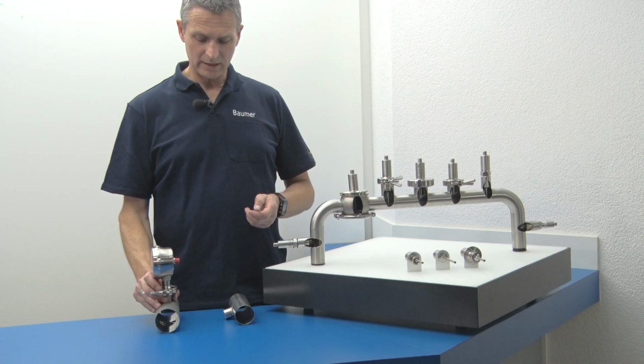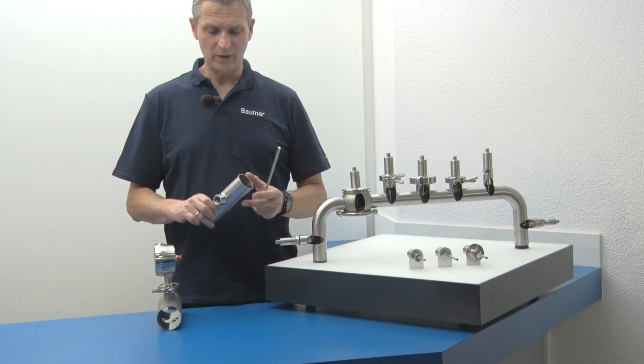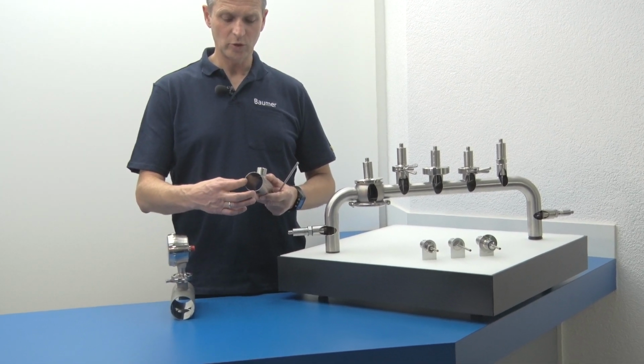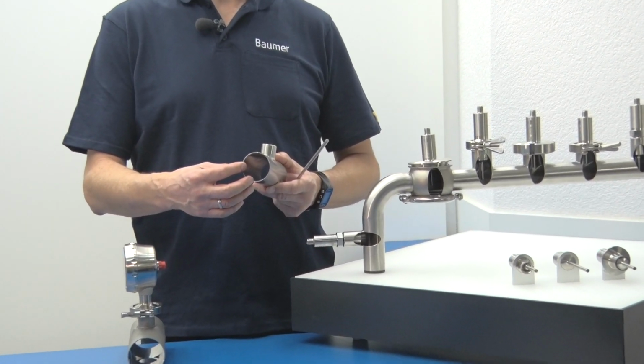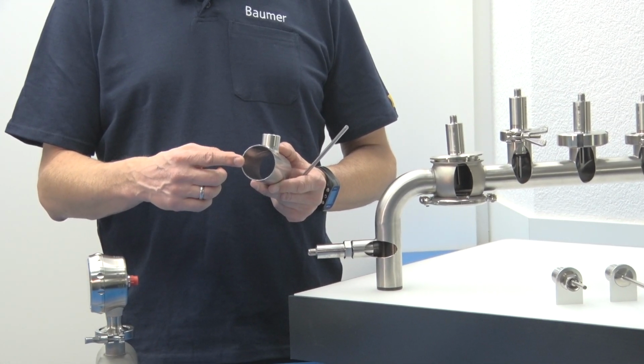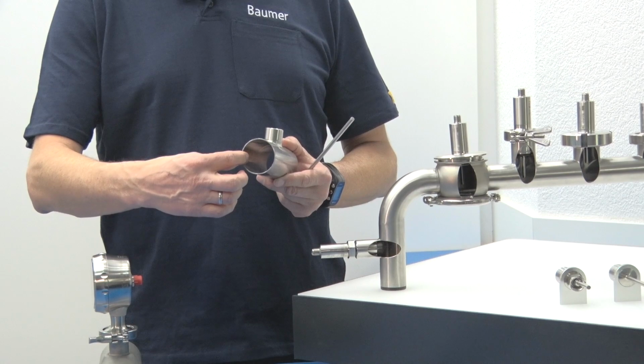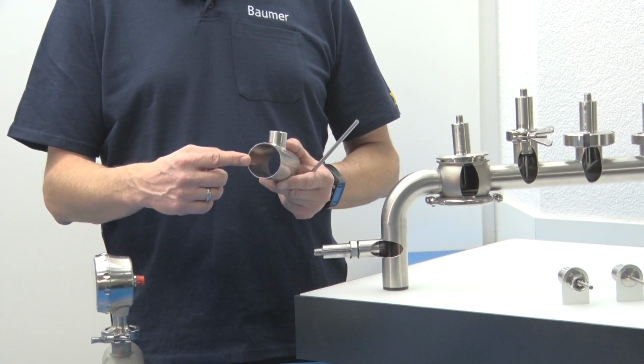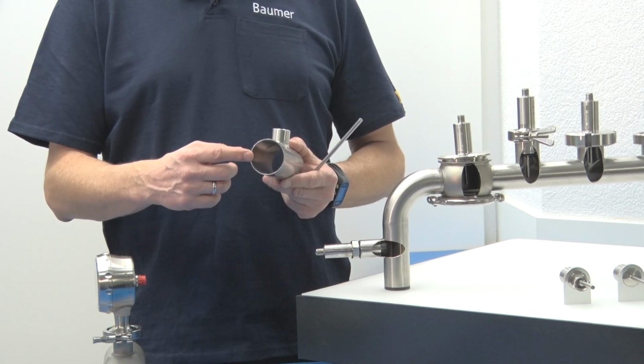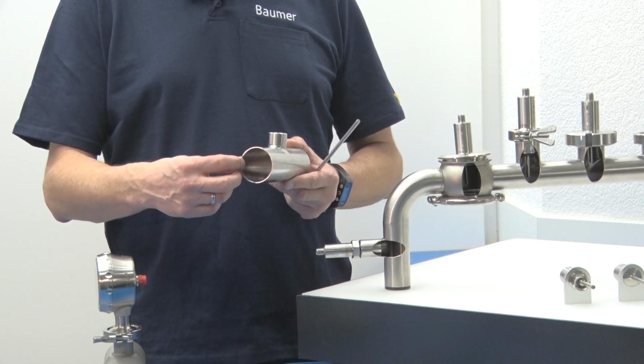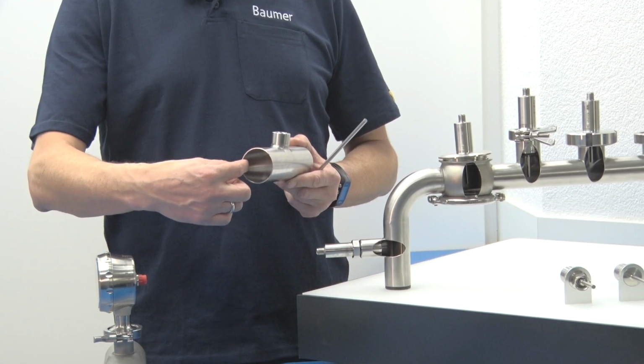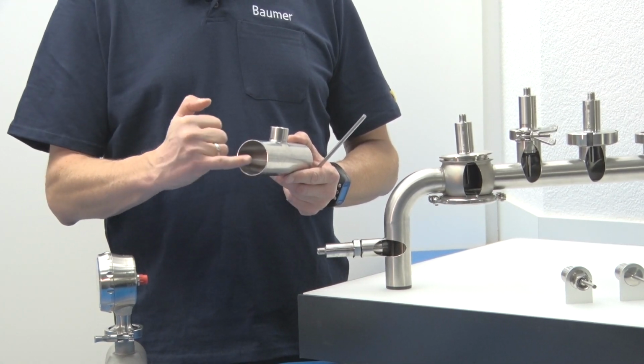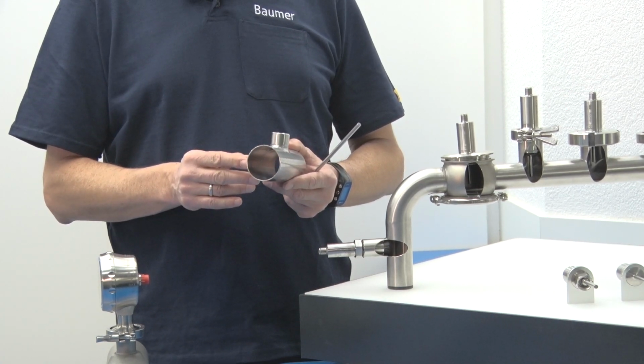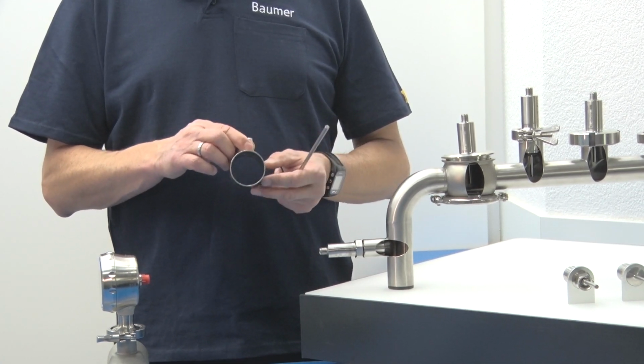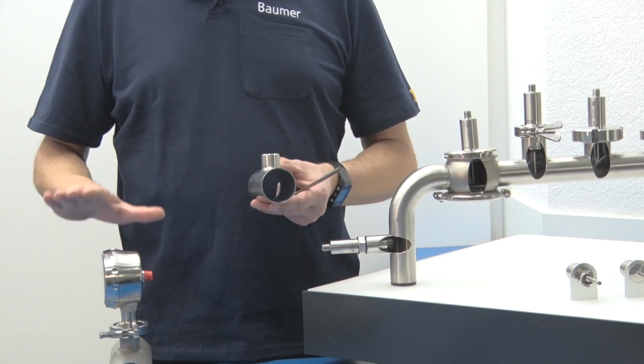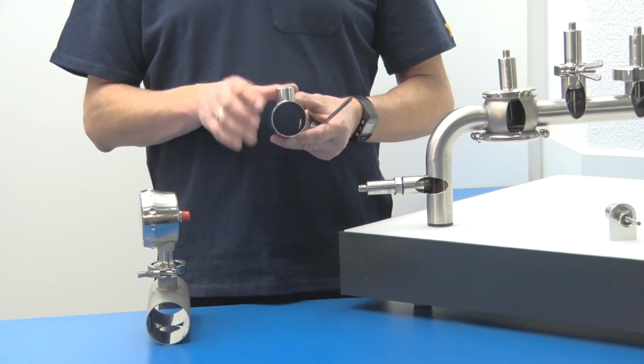It is important to consider that pipes are defined differently. The pipe diameter, specified as NPS (nominal pipe size), must be considered, along with the pressure rating PN. Another factor is wall thickness, which differs in relation to the applied nominal pressure PN - the higher the pressure, the thicker the wall. Last but not least, wall tolerances may also affect the pipe diameter. To cut it short, volume is acquired by reference measurements on a sample pipe.